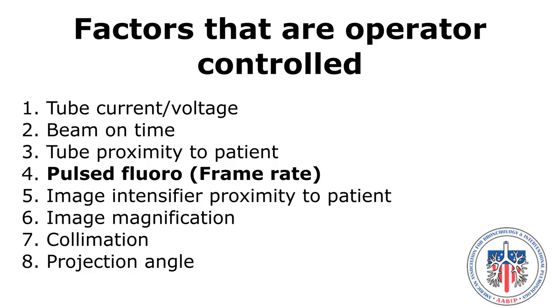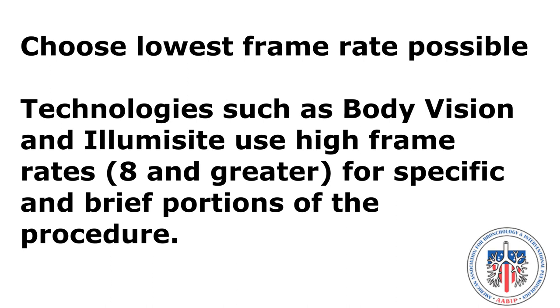Pulsed fluoro or frame rate: for routine bronchoscopy procedures, choose the lowest frame rate possible. For technologies such as Body Vision and Illumisite, use a frame rate of at least 8 or greater, but only for specific portions of the procedure. Details are discussed in the Body Vision and Illumisite videos.